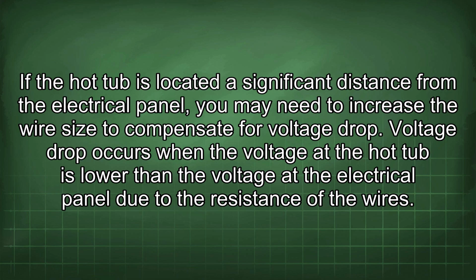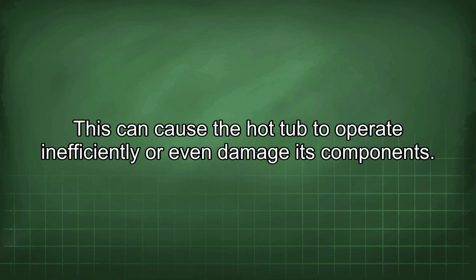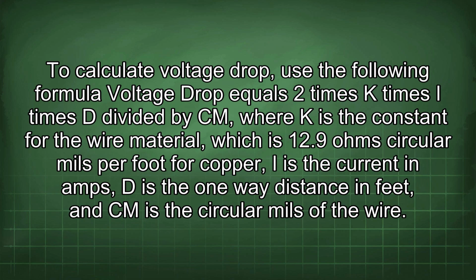Voltage drop occurs when the voltage at the hot tub is lower than the voltage at the electrical panel due to the resistance of the wires. This can cause the hot tub to operate inefficiently or even damage its components. To calculate voltage drop, use the following formula: voltage drop equals 2 times K times I times D divided by Cm, where K is the constant for the wire material, which is 12.9 ohm circular mils per foot for copper.